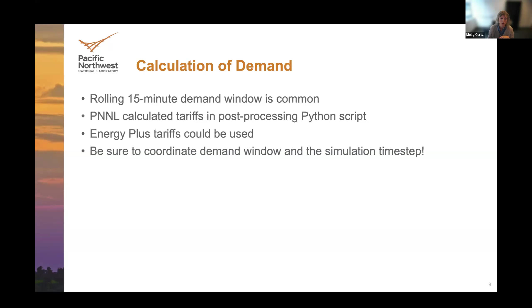I'm just pointing out here that if you have a 90 kW peak for 1 minute, that's a high value, but if you're charged based on a 15-minute average demand, that becomes only a 6 kW over that 15-minute average. So make sure you're thinking about that issue. And then on the simulation side, if there are practitioners here today, you want to make sure that your simulation time step is coordinated with that demand window so that you can do those calculations correctly.